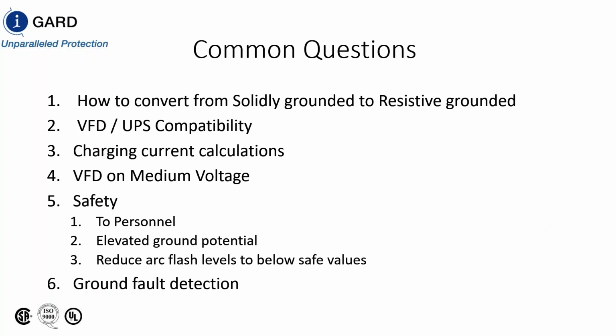So one of the things we do for training, we want to make sure that they demonstrate functional knowledge of an HRG system. So we have an annual training. It's a short class as part of all the NFPA 70E training they have to take, where they actually go on to a live 480 volt, and we energize one of the phases. It's an HRG system, and we energize a phase, and they actually take voltage readings and see that it's very minimal as far as an arc flash. You don't even see it. You just have the alarm go off on the HRG. Okay.